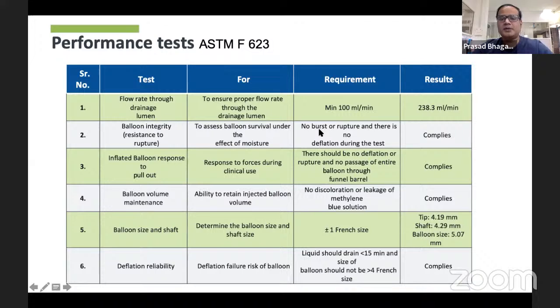The requirement is that the balloon should neither burst nor rupture during the deflation test. What we have done is inflate the balloon and keep it in artificial urine for 7 days at 37 degrees Celsius. In that time, the balloon should not rupture and should not burst. Our SilverGuard Foley balloon catheter has passed this test also, because this is very important. As I said, the balloon is the most important part of the catheter, and in this guideline there are 4 tests dedicated only to the balloon. The third one is inflated balloon response to pull out, and usually this is for the response of forces during clinical use.